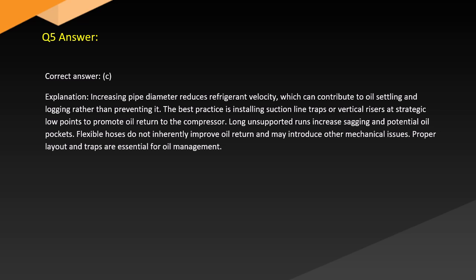Increasing pipe diameter reduces refrigerant velocity, which can contribute to oil settling and logging rather than preventing it. The best practice is installing suction line traps or vertical risers at strategic low points to promote oil return to the compressor. Long unsupported runs increase sagging and potential oil pockets. Flexible hoses do not inherently improve oil return and may introduce other mechanical issues. Proper layout and traps are essential for oil management.